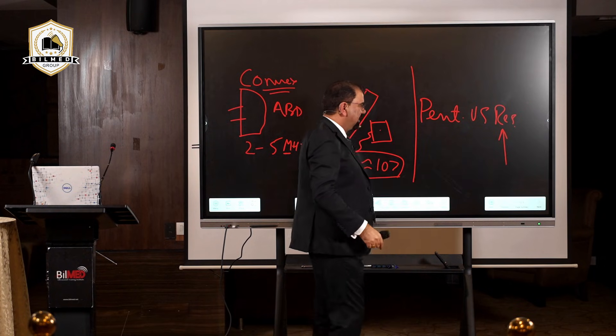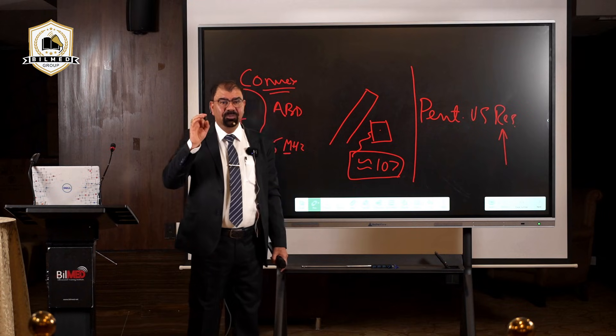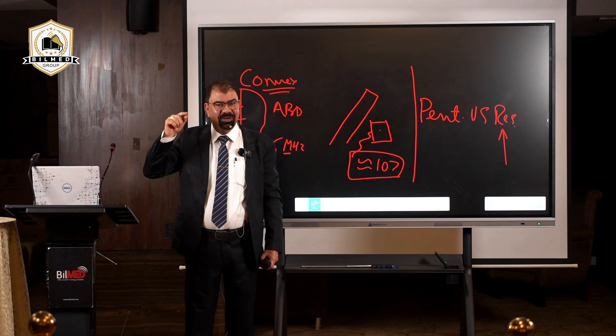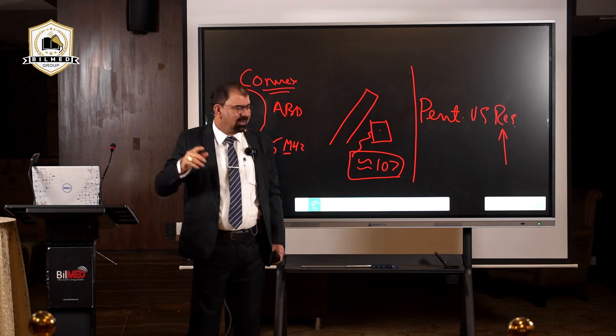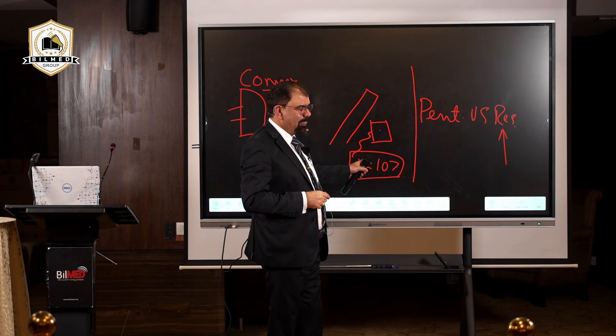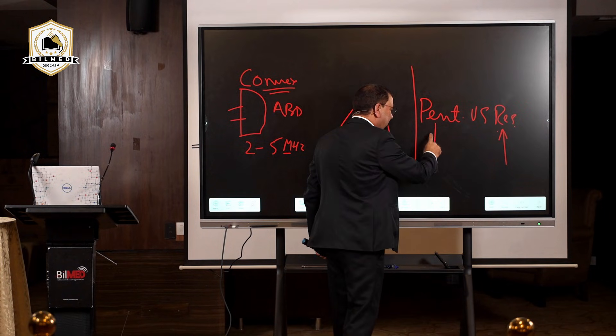Try to understand what is deciding the resolution. Resolution is decided by frequency, and that frequency is decided by wavelength. When I am having a high frequency probe, the resolution will be more but penetration will be less, and vice versa.